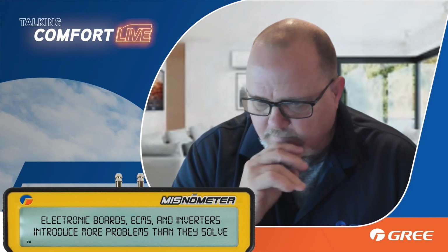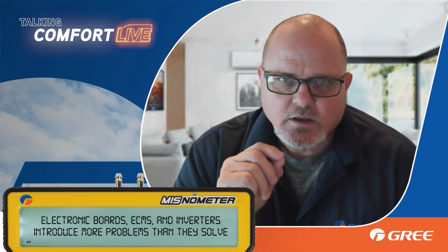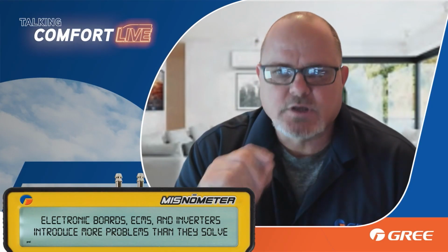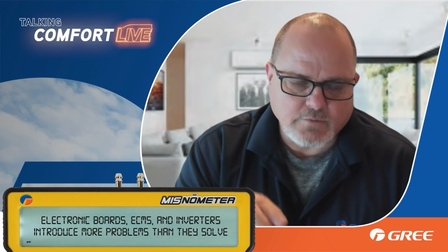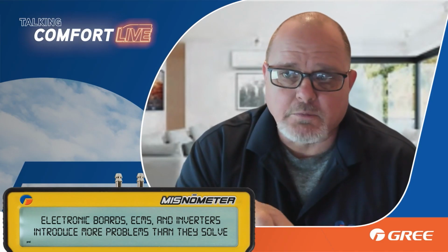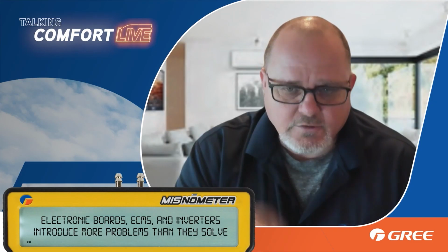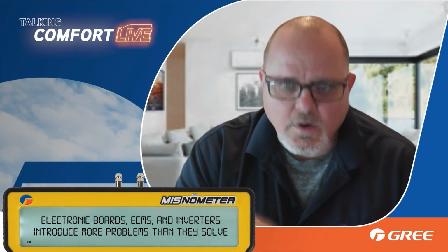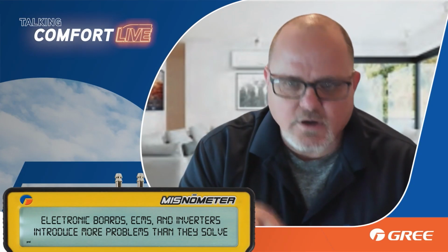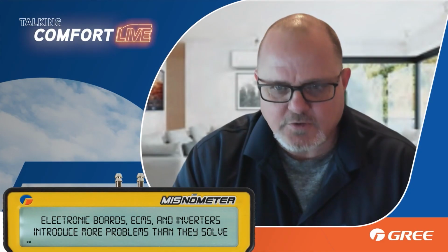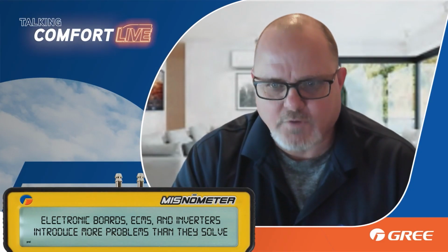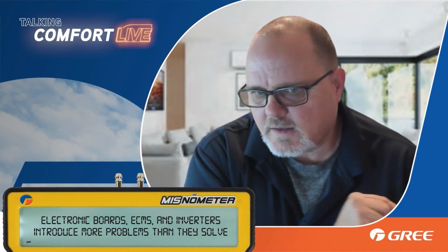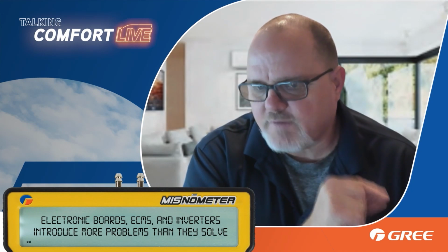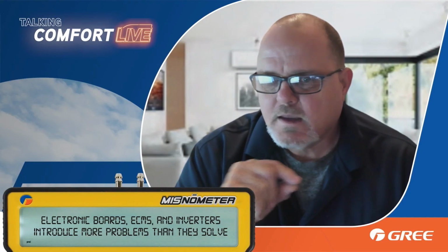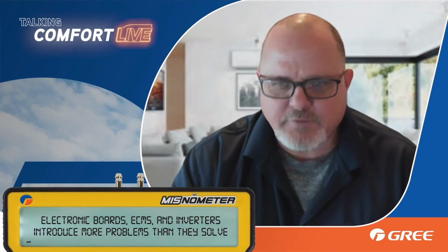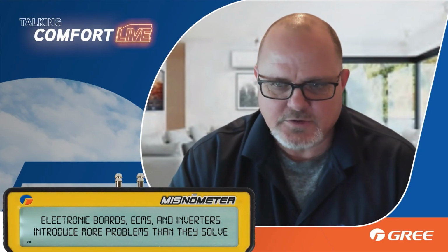Well, my response to them was, if you haven't gotten into using furnaces and air handlers with inverter-driven, or not inverter-driven, I keep going the wrong way, variable speed blowers or ECM blowers, you need to start, because that technology is not going away. But the technology that I can assure you is going to go away is the PSC fan motors that you've dealt with your entire career thus far. The government had already put in that ban and slowly phasing out incandescent bulbs. I just knew it was coming. I knew they were going to phase out PSC fan motors, and they did.